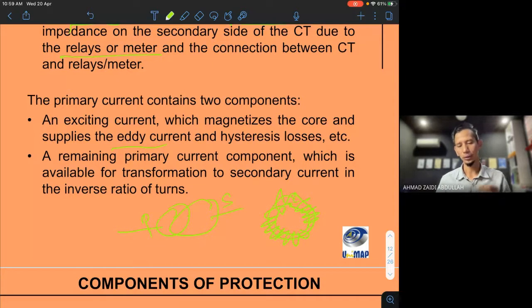coil. This coil, when we have current flowing through this CT, will be magnetized. When we have a current through the coil, the coil will be magnetized, and from the magnetization it will produce the magnetic flux. And then this we call the eddy current, and the losses, hysteresis losses. This current is what we capture, from 100 amp to become a very low amp, that's the concept.